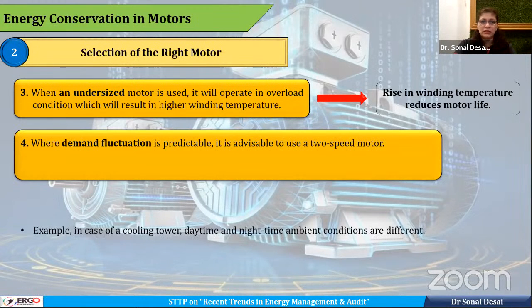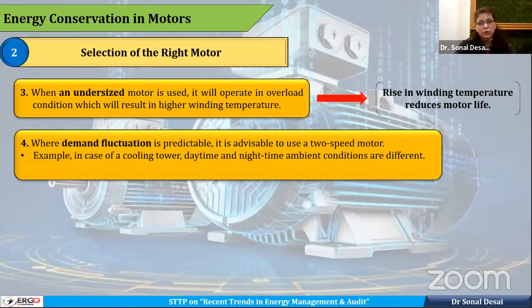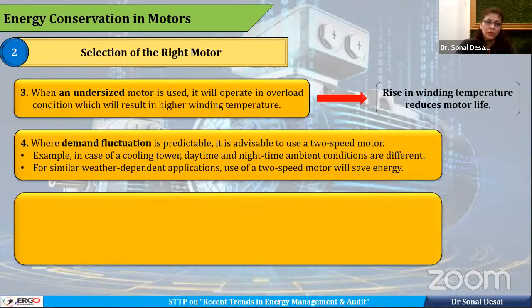And when there is a predictable demand fluctuation, always go with the 2-speed motor. As just given a case of a cooling tower, during night time and daytime, different flow rate is required. So over there, don't run the single motor. Use twin motor or use the 2-speed motor. So over there, it will have power optimized. For a similar weather dependent application, use of 2-speed motor will save the energy.